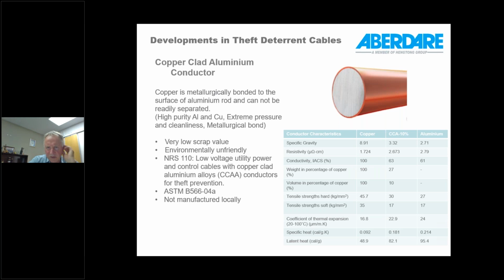The weight as a percentage of the copper is low for CCA, 27% that of copper, and the volume of copper is only 10%, as defined by the 10% name that's given to this particular version. You also get a 15%, but I would say 10% is probably the most used. Tensile strength is quite a bit lower than copper. Coefficient of expansion is also significantly different, and of course this is where some of the problems come in between, let's say, aluminium and copper: the rate of expansion is different, and you get loosening of connections when you're using small sizes of aluminium. But this has really been addressed by copper-clad aluminium and the use of 8000 series alloys within these type of conductors.